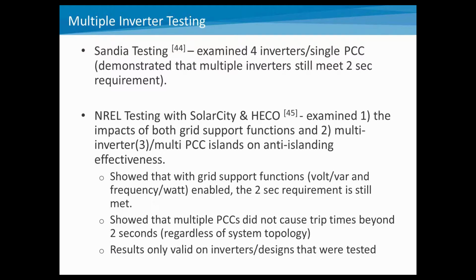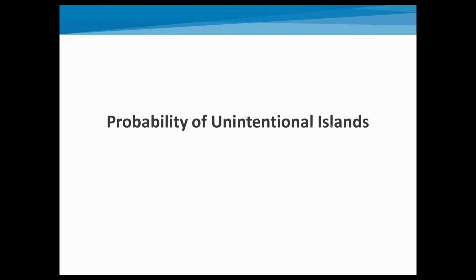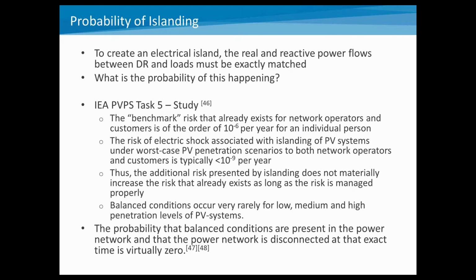So one of the things that we would point out from this result is obviously these results are only valid for the inverters and designs that were tested, but they do show that the ones that I would say are popular designs that are out there do meet these types of requirements when looking at multi-inverters. One of the big challenges we have with addressing this is the fact that it's going to probably be impossible to test all the different types of deployments in all scenarios under all conditions. And so one of the things that you really have to look at is what's the probability of these island conditions actually occurring and happening. So as I move on in the presentation, we'll discuss the probability of unintentional islands.